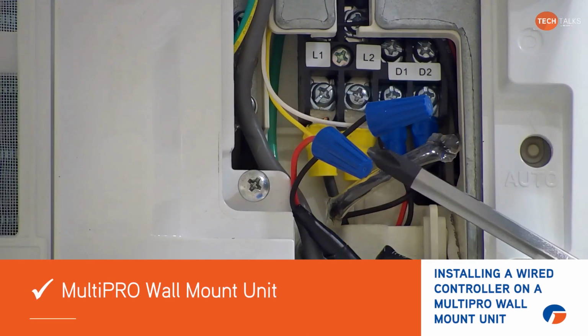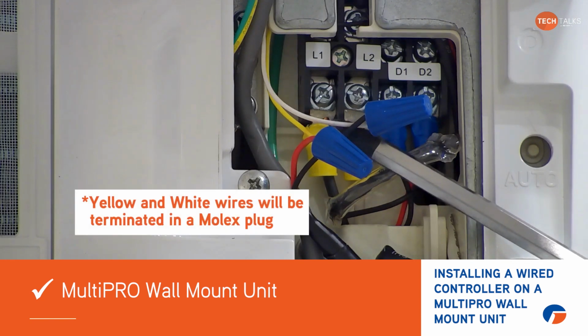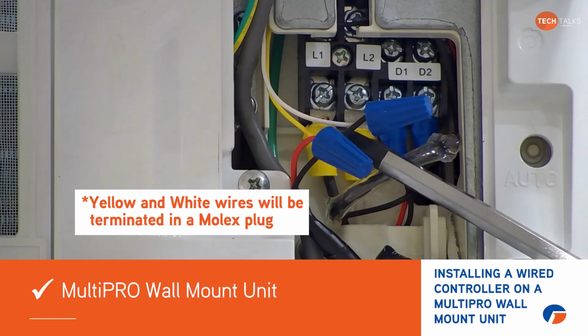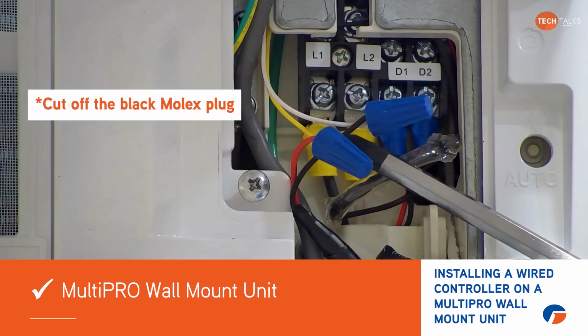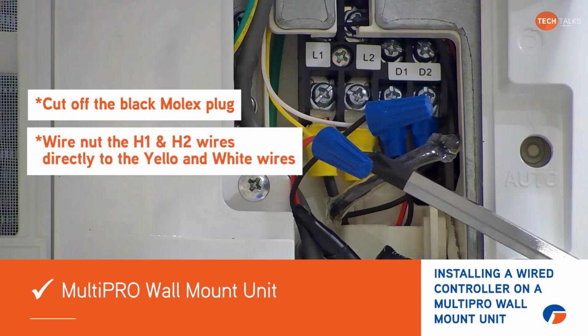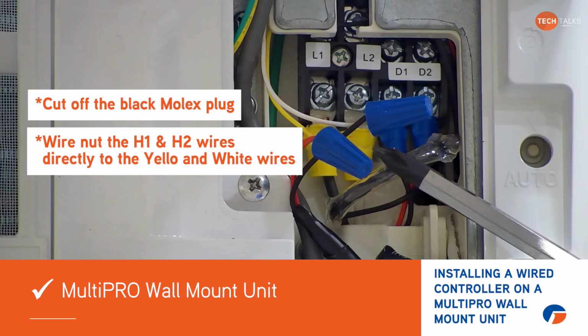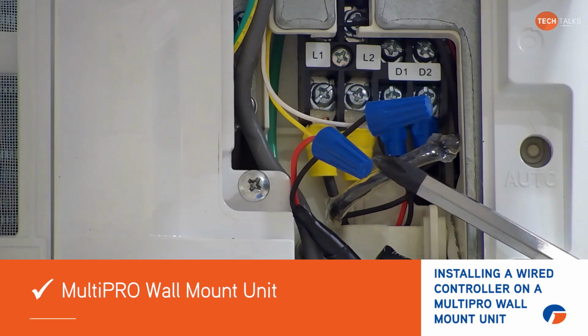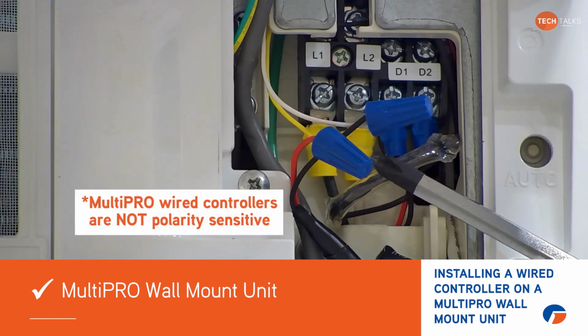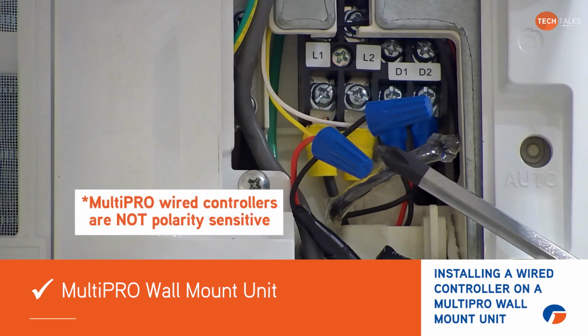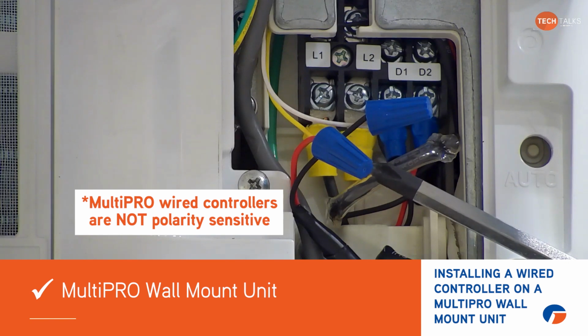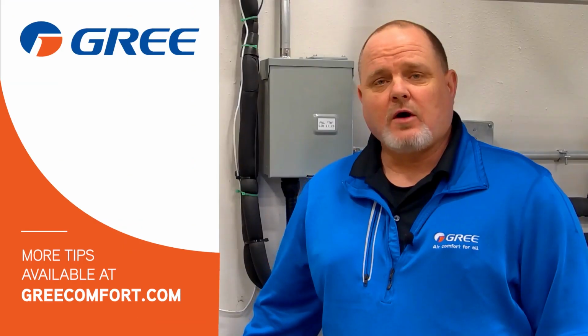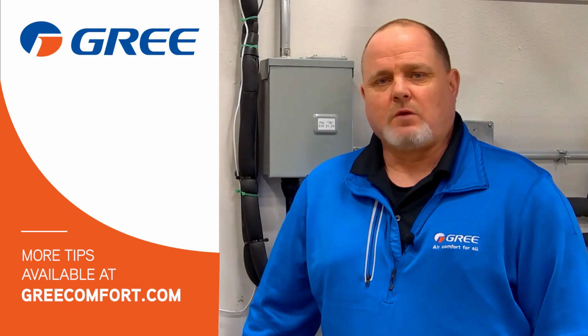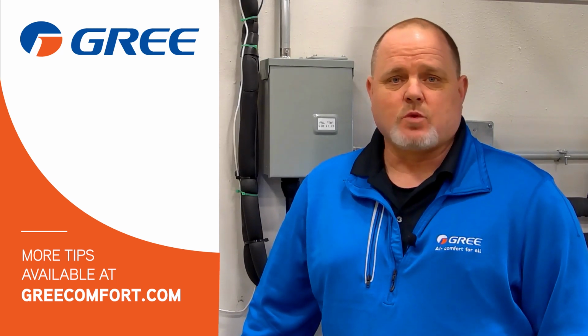This unit already has a wired controller hooked up to it, but you'll find these yellow and white wires dangling down, terminated in a Molex plug. All you need to do is cut off that black Molex plug and wire nut your H1 and H2 wires directly to that yellow and white wire. Again, with all MultiPRO systems, the wired controllers are not polarity sensitive, so you don't need to worry about which one is which when you hook it up. Just pick one wire on white, one wire on yellow, and it doesn't matter on the back of the wire controller whether that's going to H1 or H2. So I hope that helps you in installing a wire controller on a MultiPRO wall mount unit that does not have the H1, H2 connections.